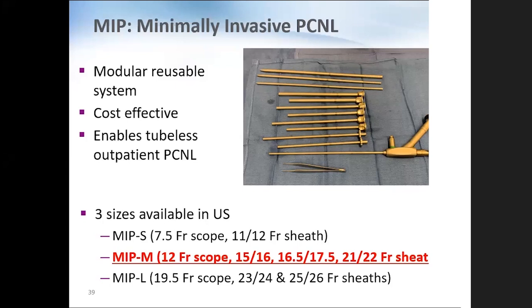In the United States, there are three main size sets designated small, medium, and large, or MIP-S, MIP-M, and MIP-L, and that really refers to the size of the nephroscope, the camera. So we primarily use the MIP-M set, which is a 12 French scope, and it comes with three different sheath sizes that range from a 15 or 16 French, 17.5 French, and a 22 French. And you can see those laid out here. Each sheath comes in two lengths. There's a regular length and then a length designated with an S for supine, which is to facilitate if you're doing the case in a prone versus a supine position. It's slightly longer to account for the increased skin to stone distance for a lower pole in the supine position.